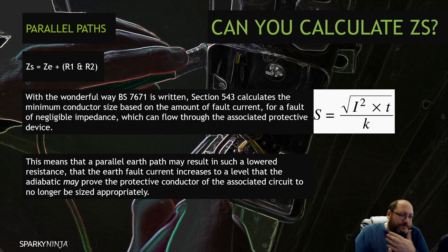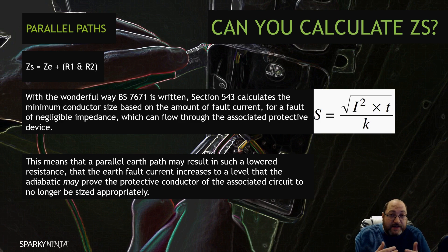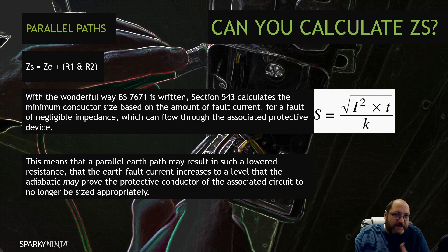It might be that a parallel has resulted in your protective conductor being too small all of a sudden — just a knock-on effect. If you calculate without measuring, you're not going to find any of this information out. It could be that you calculate something, install it, and the protective conductor is now undersized — under an earth fault condition there is thermal constraint and it gets damaged.